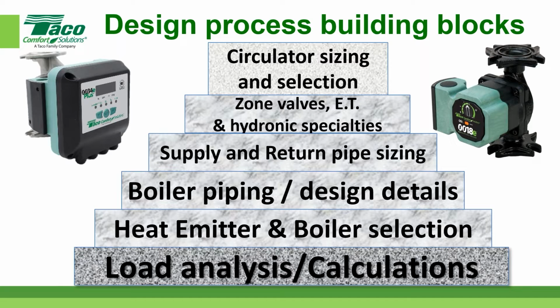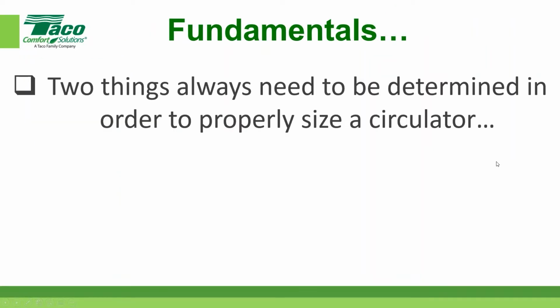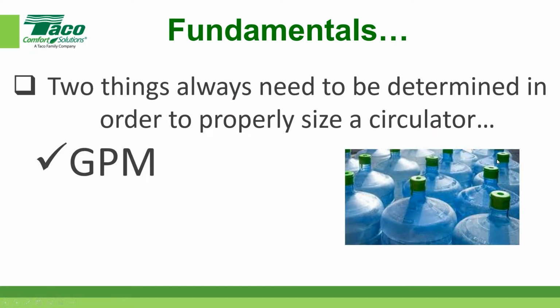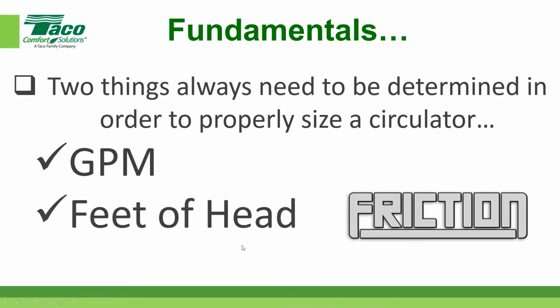So, we're not going to cover all this stuff. We're going to cover quite a bit, and we're going to hit the points that have to do with circulator sizing for the most part. The first fundamental thing we need to know is, well, two things here. In this case, we need to know what the gallons per minute is, and then we need to know at that gallons per minute, what's the resistance or the friction or the feet of head that the circulator is going to experience? And we'll go through that one thing at a time.